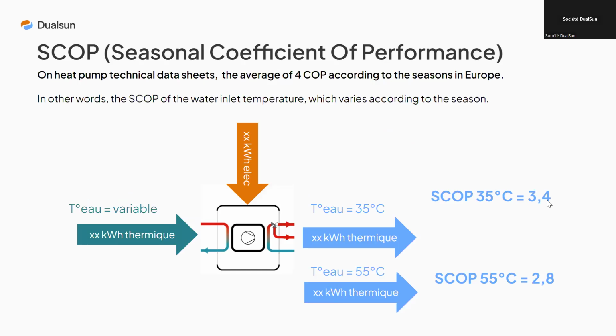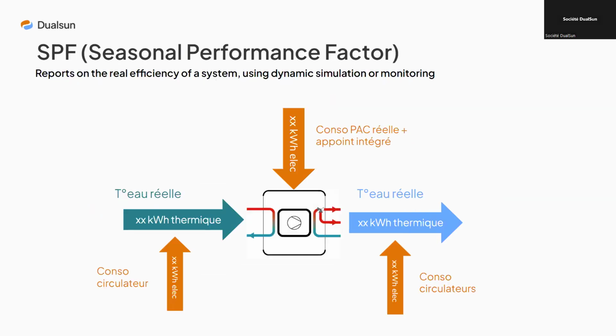We also talk about the SCOP. Here we add the term seasonal. The difference here will be the temperature of the glycol water entering the system, which will be variable as outdoor temperatures vary according to the season. And finally, we're going to talk about the third and last term that will be of particular interest to us, the SPF, seasonal performance factor, which will give an idea of the performance, not just of the heat pump, but of the system as a whole. In other words, the real efficiency of a system from a dynamic simulation or monitoring. So it's really the design of the whole circulators. We could also compare the COP to the power in watt peak of a panel and the SPF, which will be more the total average power of the panel or the installation, or maybe the predictable power, taking into account the transformation of the current of the whole system.